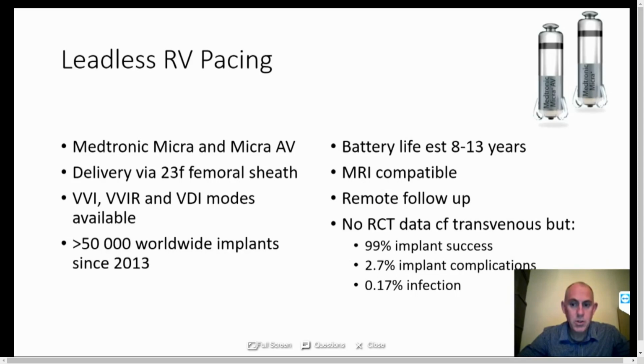This is delivered via a 23 French femoral sheath. In the case of the Micra, it can pace in VVI and VVIR modes. The Micra AV paces in VDI mode, and the way it does that is not via electrical sensing but via an accelerometer, which detects the atrial contraction and syncs from there.